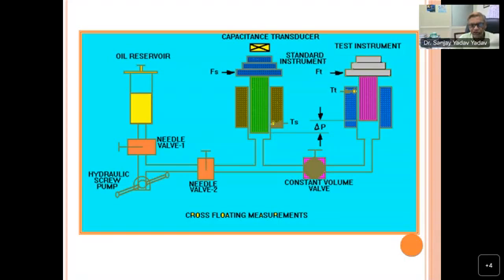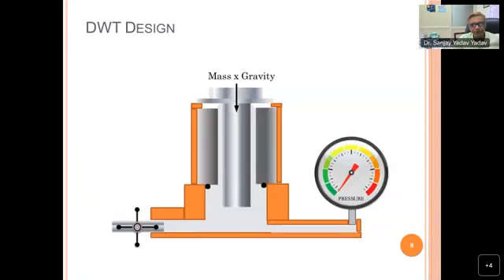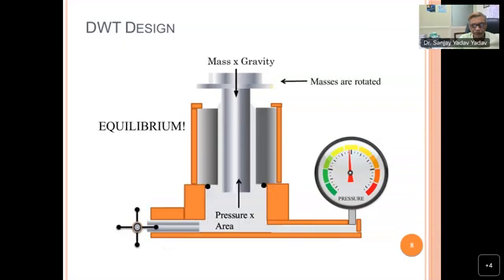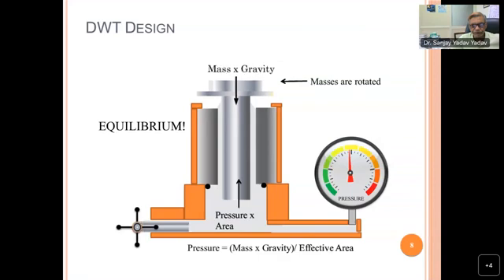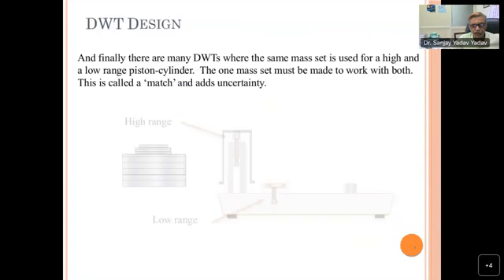But the moment you open the constant volume valve, immediately you will find which pressure standard is heavier and which one is lighter. So you can adjust the mass on the standard and determine the exact pressure value. So this is the simple calibration procedure by this experimental setup. One short animation of this you can see. You can apply pressure from this to lift the piston at the reference plane. And then this pressure is transmitted to the pressure dial gauge, and then you can discharge if required.